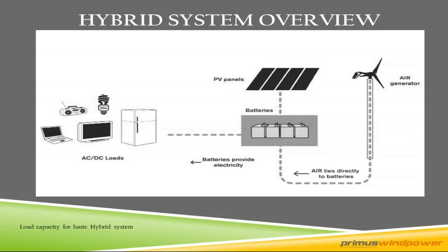If you're using a smaller battery bank than the minimum recommendation, we need to talk about your loads and other factors. The reason is that the turbine can push a lot of amps — say 30 or 40 amps — and if you have a 100 amp-hour battery bank, the voltage is going to rise very rapidly and the turbine will shut down. It will then shut down, the voltage will drop back to resting voltage, the turbine starts back up again, and if this continues for weeks or months, the circuit card can become damaged, causing premature failure.